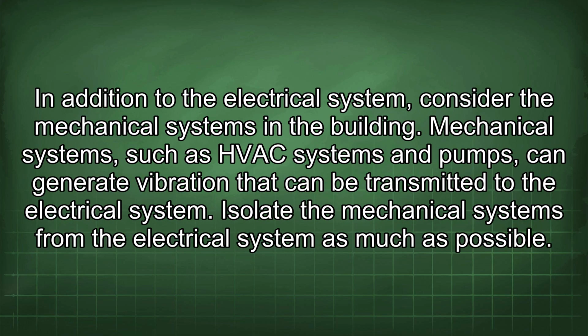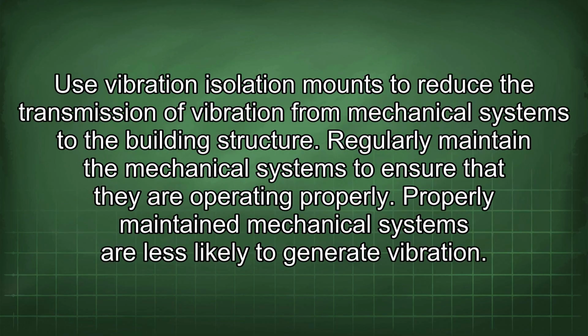In addition to the electrical system, consider the mechanical systems in the building. Mechanical systems, such as HVAC systems and pumps, can generate vibration that can be transmitted to the electrical system. Isolate the mechanical systems from the electrical system as much as possible. Use vibration isolation mats to reduce the transmission of vibration from mechanical systems to the building structure. Regularly maintain the mechanical systems to ensure that they are operating properly. Properly maintained mechanical systems are less likely to generate vibration.